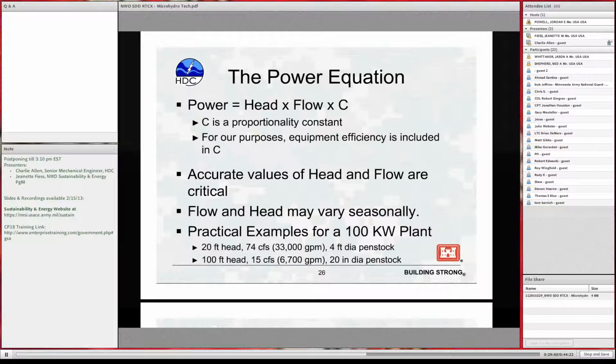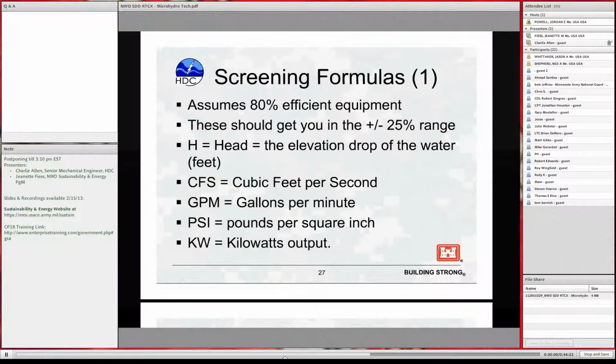And the size of the penstock here is a little bit important because the physical size of the equipment, the dimensions, if you will, of the turbine and generator are generally proportional to the size of the penstock that's feeding it. So physically smaller equipment means physically cheaper to build. The bottom line here is the more head you have, the higher the pressure you have, the cheaper it is to install the equipment and the easier it is to get payback for your investment.